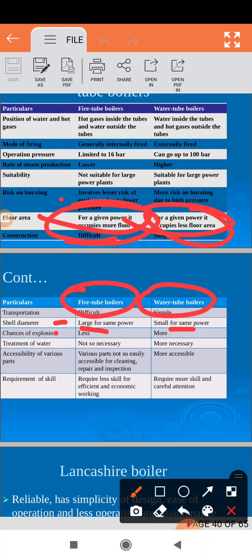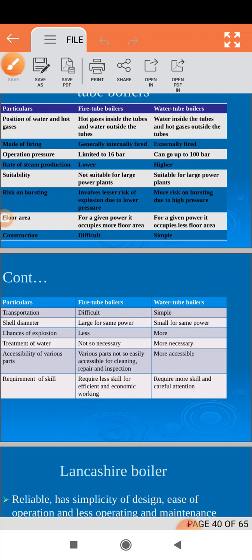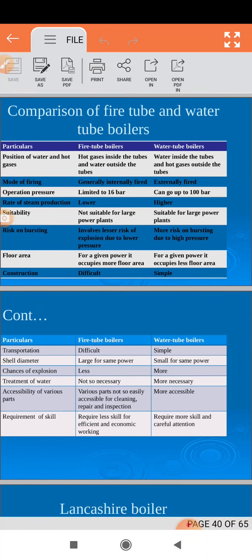Chances of explosion: as discussed, fire tube has less risk and water tube has more risk. Regarding treatment of water: in a water tube boiler, water flows inside the tubes — if hard water is used, impurities deposit on the inner surface forming scale, which can cause tubes to fail. Therefore, water treatment is essential for water tube boilers. For fire tube boilers, fire is inside the tube so there is no such scaling issue — water treatment is not strictly required. Accessibility of parts: fire tube boiler parts are not easily accessible; water tube boiler parts are easily accessible. Requirement of skill: fire tube requires less skill for operation, while water tube boilers require a higher skill level from workers.